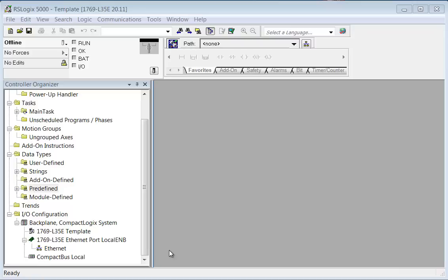So with the CompactLogix, there may be one or more ports on the front of the processor and maybe one on the back connecting it to the backplane. ControlLogix typically has an RS-232 9-pin sub-D shell on the front. Now they also have USB on the front. But up until recently it was just RS-232 on the front and then the ControlBus port on the back. So the connector on the back of a processor in this platform is a communications port to the backplane, because the backplane is a network, at least for 1756 chassis and 1756 processors.